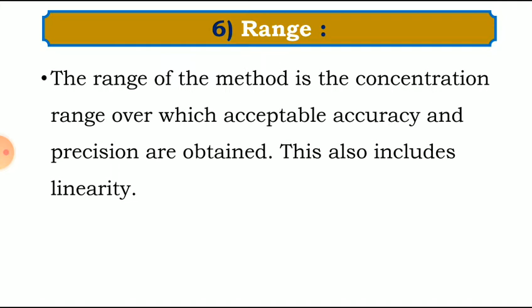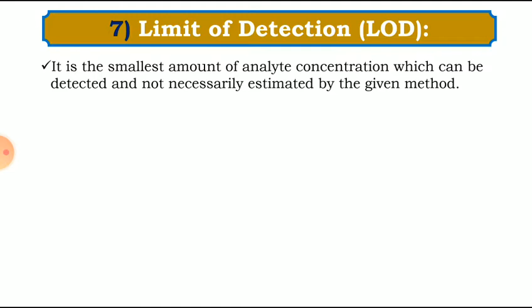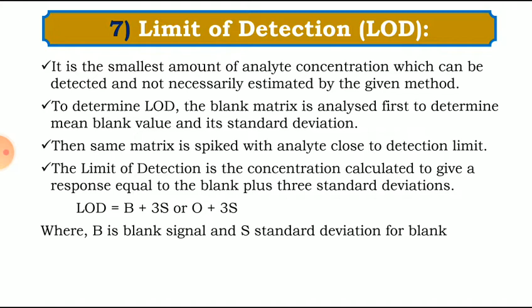Seventh number, limit of detection, in short LOD. It is the smallest amount of analyte concentration which can be detected and not necessarily estimated by the given method. To determine LOD, the blank matrix is analyzed first to determine the blank value and its standard deviation. Then the same matrix is spiked with analyte close to the detection limit. The limit of detection is the concentration calculated to give a response equal to blank plus 3 standard deviations. The relation given is LOD = B + 3S, where B is the blank signal and S is the standard deviation for the blank.